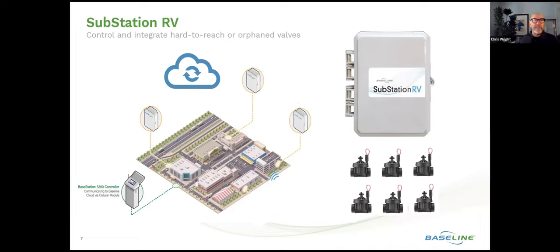As we talk about this as wireless two-wire — where's the wireless aspect? Baseline's two-wire sends and receives data, sends a signal out to a baseline decoder, the signal comes back to the controller: it's a two-way data communication protocol. What Baseline has engineered is a way to take that same protocol, but instead of sending it down a physical two-wire path, it goes to the cloud down to the substation and is received there. Then it goes back through the cloud to the controller. So we have this two-way communication protocol going through the cloud instead of a wire path.